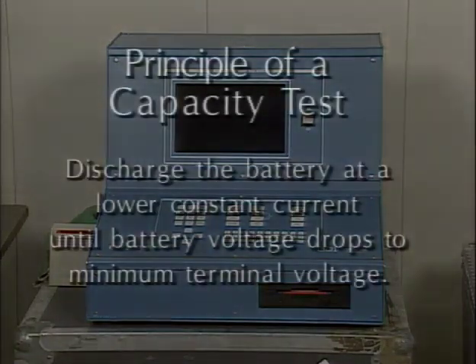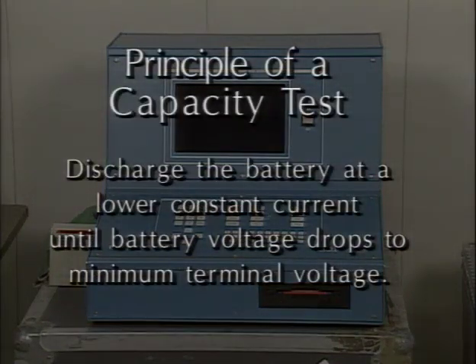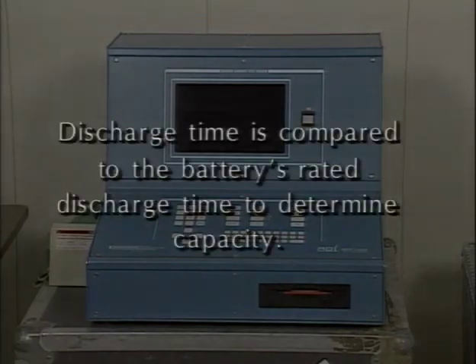The principle of performing a capacity test is to discharge the battery at a lower constant current until battery voltage drops to a minimum terminal voltage. The time it takes to discharge the battery to the minimum terminal voltage is compared to the battery's rated discharge time to determine the capacity of the battery.